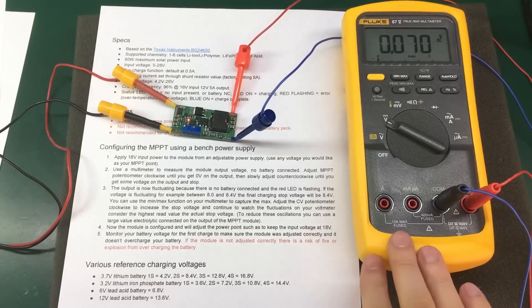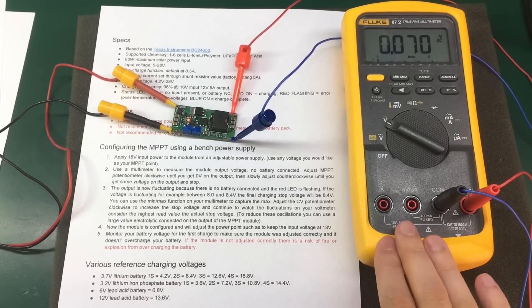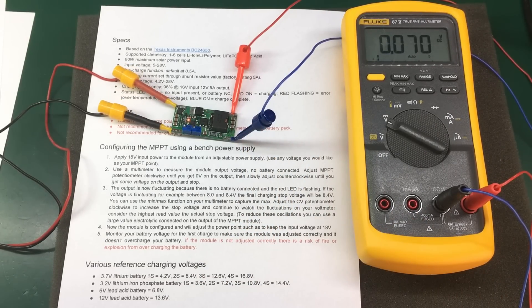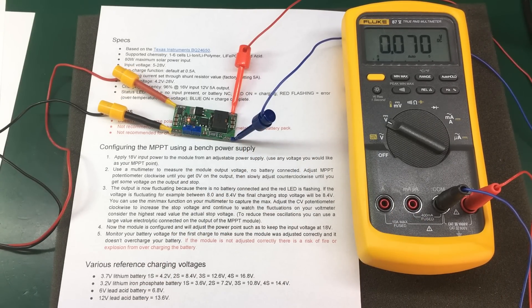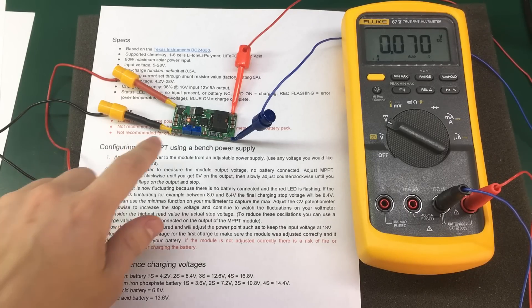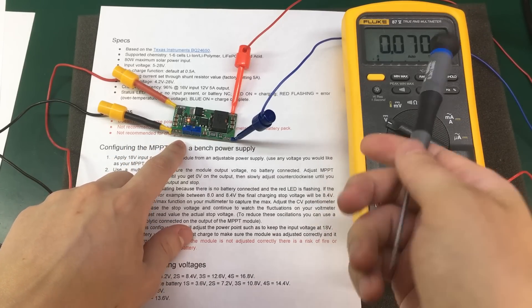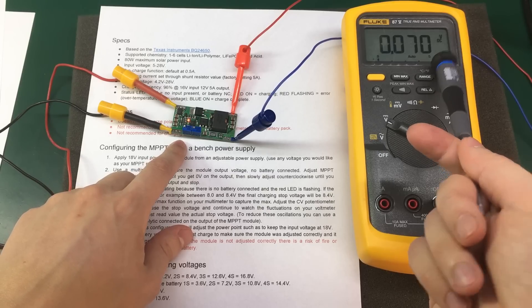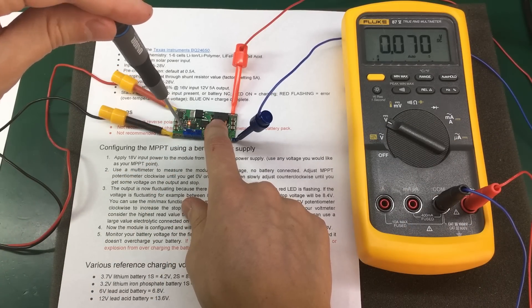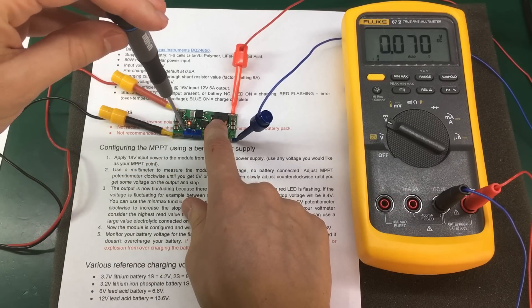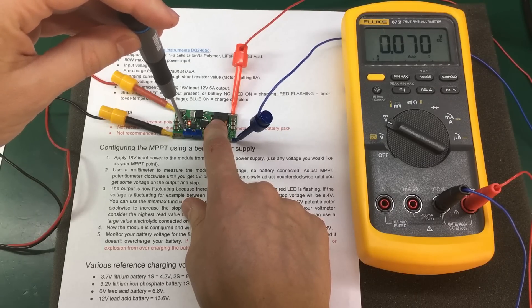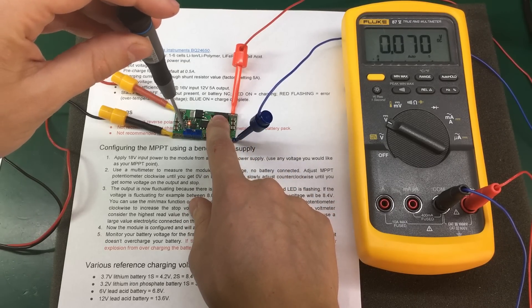You also need a multimeter on the output of the module to measure the output voltage. You don't have any battery connected. Next, you need to adjust the MPPT pot, which is this one on the left, until you get 0V on the output. Then you slowly adjust counterclockwise until you get some voltage on the output and stop immediately.